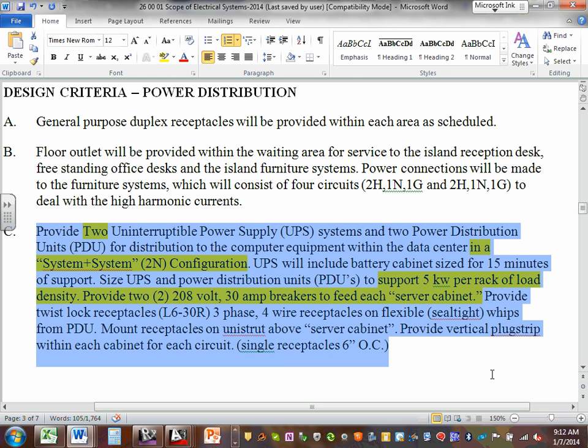The idea is that when you lose power, your generator is going to start. That takes, depending on the situation, maybe 10 seconds, unless they're parallel multiple generators, which might take a minute or two. During that time, your utility's out and your generator is starting, so you don't have power. That gap is dealt with by the batteries, which feed the load.